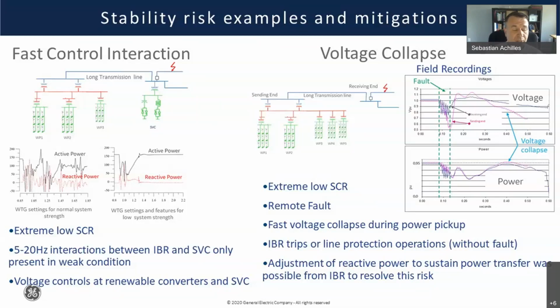If we think of voltage collapse associated with load behavior, which the industry has studied for many years, that was slower because the active power behavior of loads has much slower dynamics. This plant issue, many years ago, was resolved by slowing down the active power recovery and modifying the reactive power control so there was enough reactive power to sustain the power transfer.